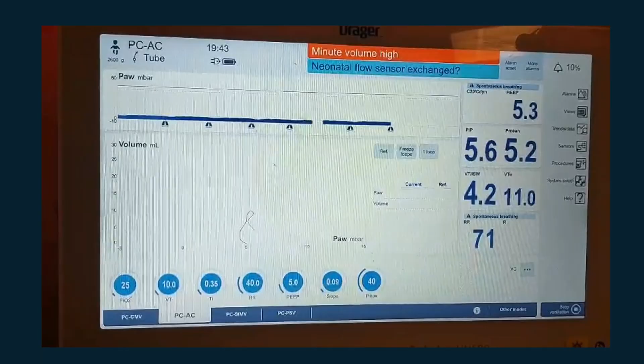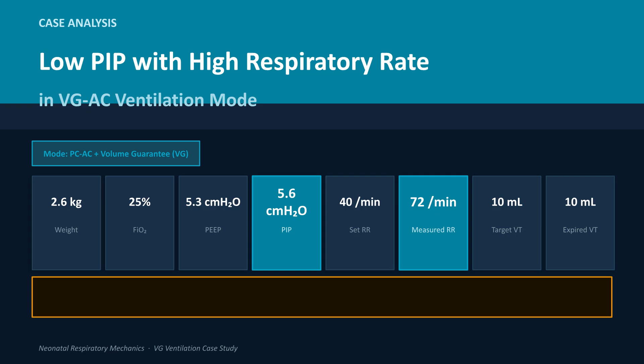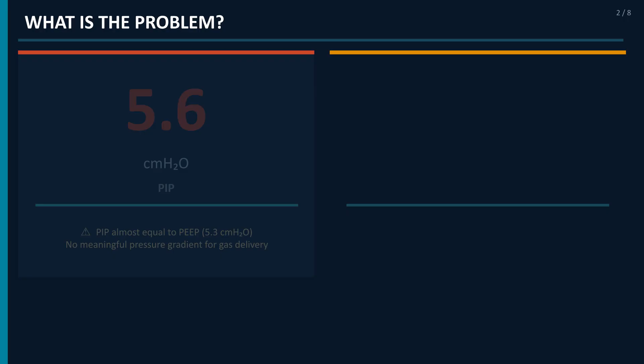We are reviewing a case presenting with low peak inspiratory pressure, or PIP, but a high respiratory rate, or RR, in VGAC mode. The patient's weight is 2.6 kilograms, and the set respiratory rate is 40 per minute, but the measured RR is 72 per minute. Crucially, the expired tidal volume matches the target tidal volume of 10 milliliters. We also observe that PIP is very close to PEEP, creating a near-zero pressure gradient for gas delivery.